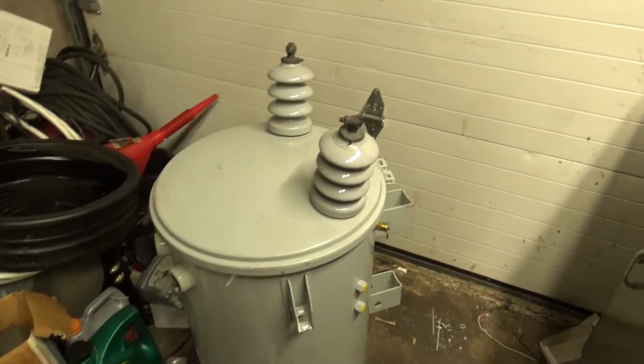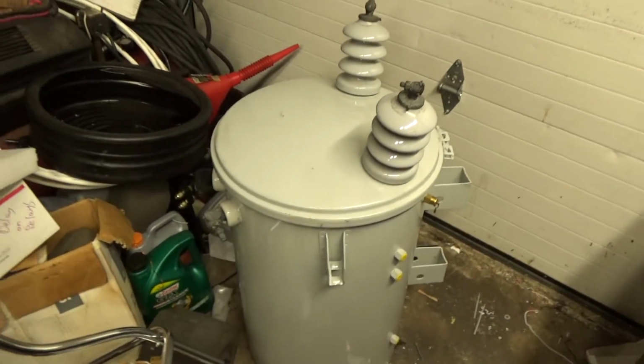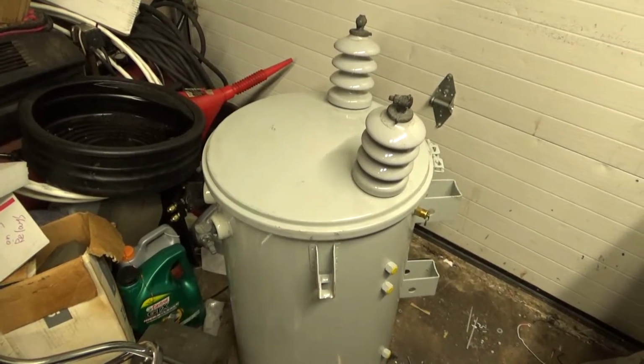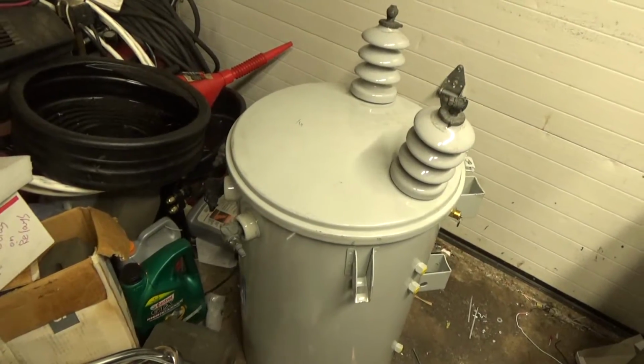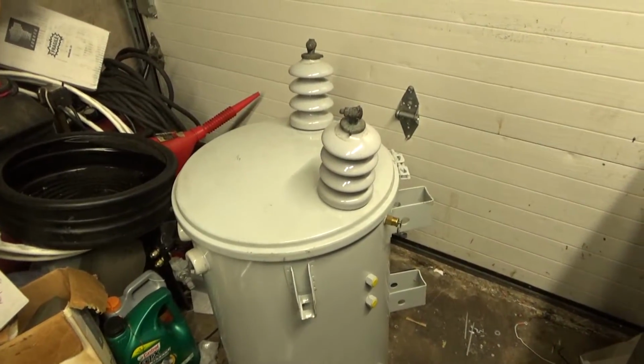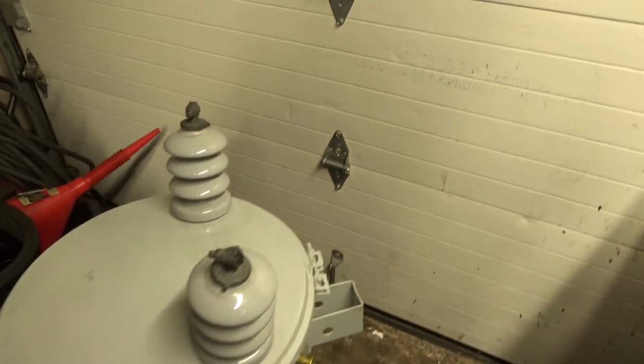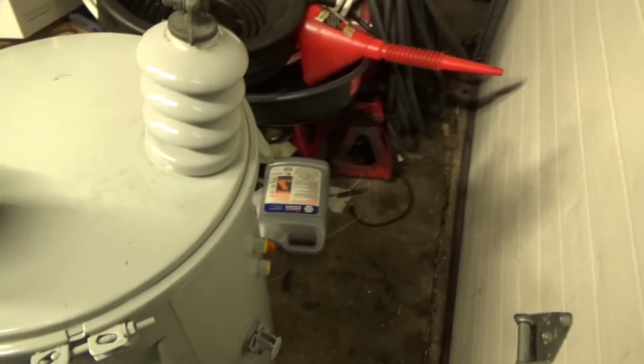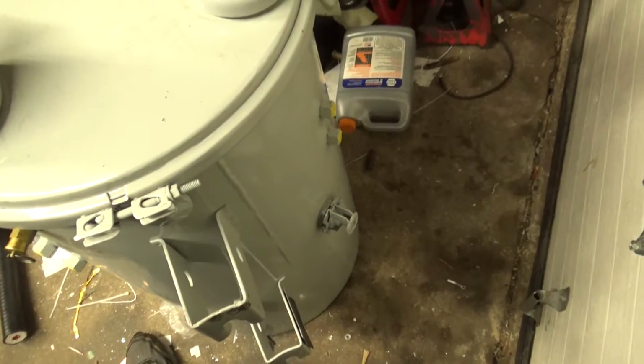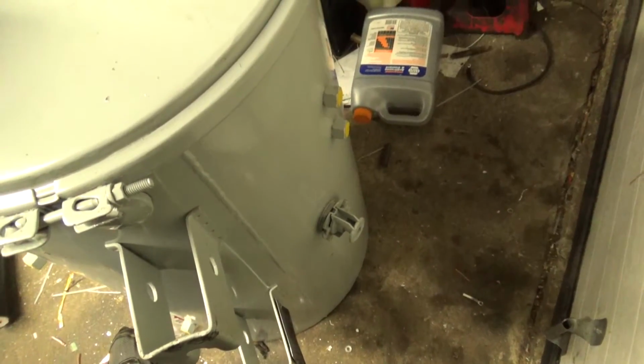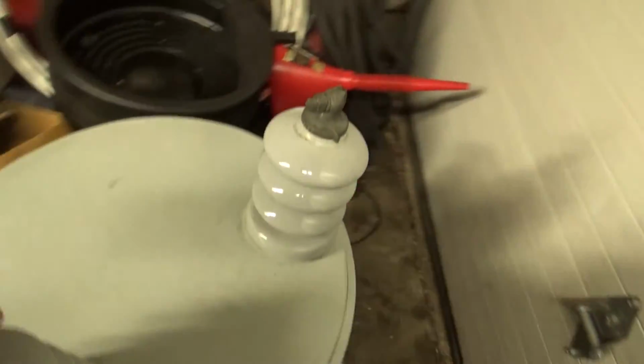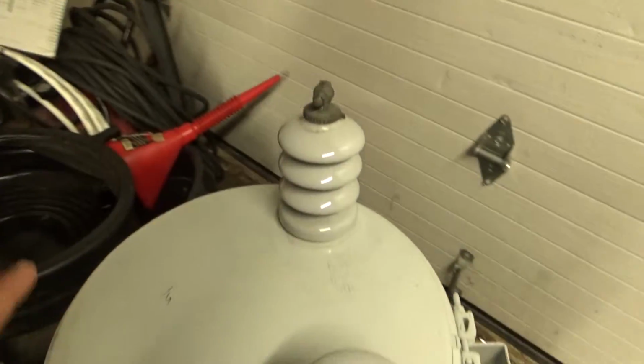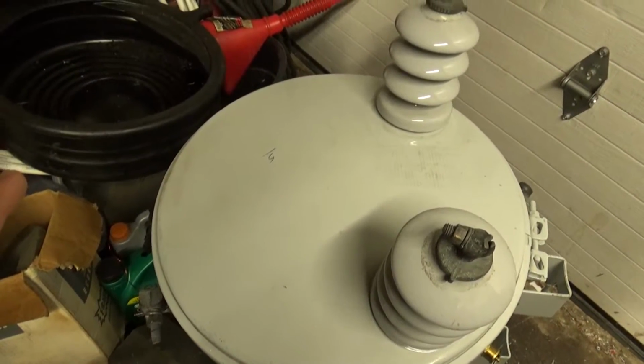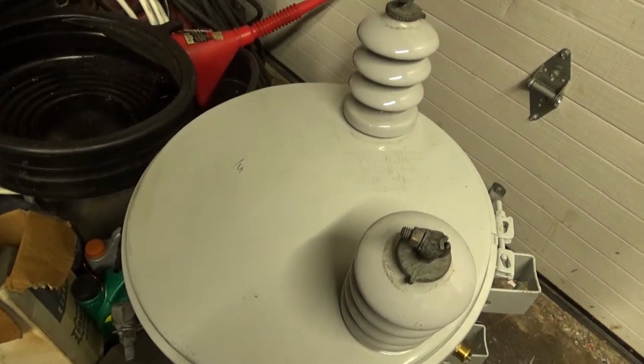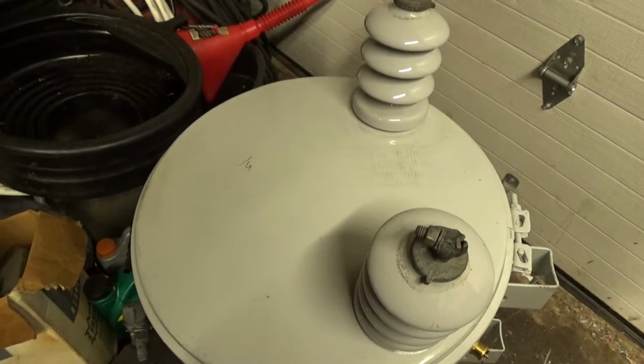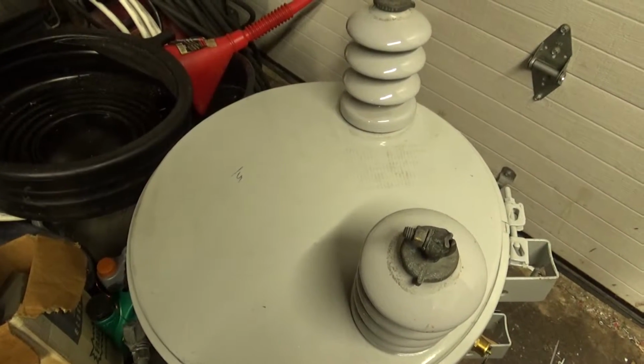this one's 25 kVA, 5500 volts. That equals out to 4.54 amps. It actually has a percentage switch on the side right there, which allowed the power company to adjust the transformer on the pole. See, this was custom wound to this voltage, but this isn't a standard voltage. More standard would be like 4800, 7200, and so on.